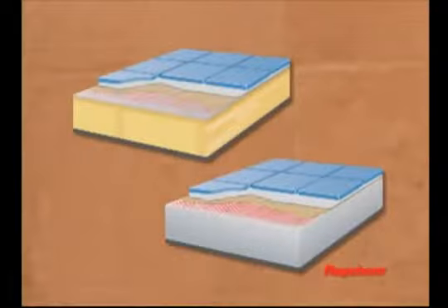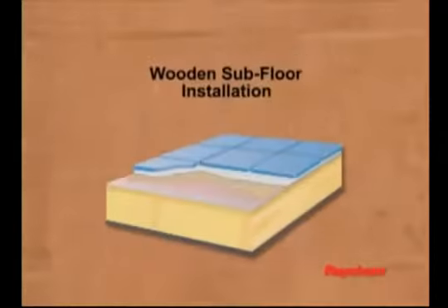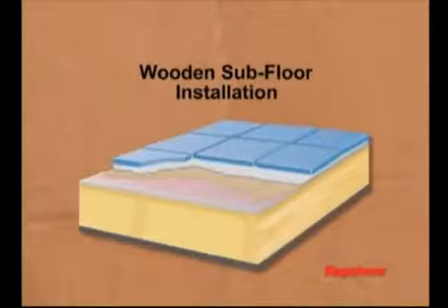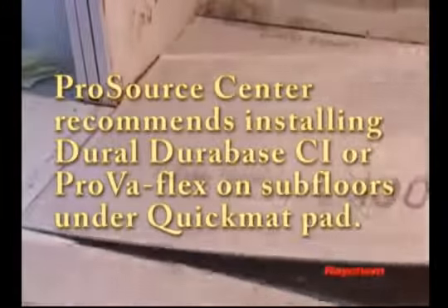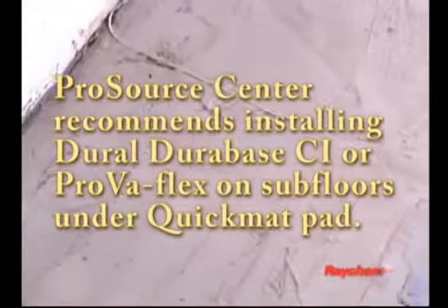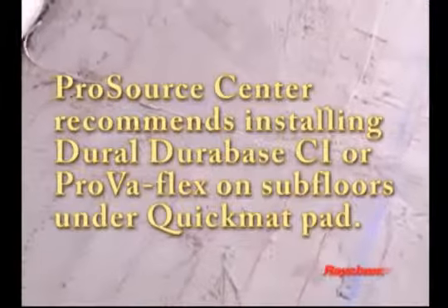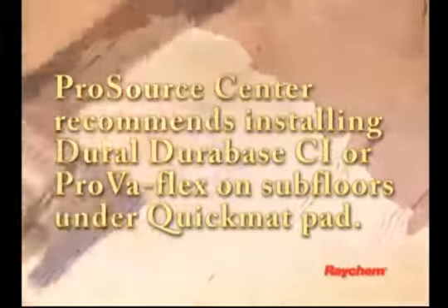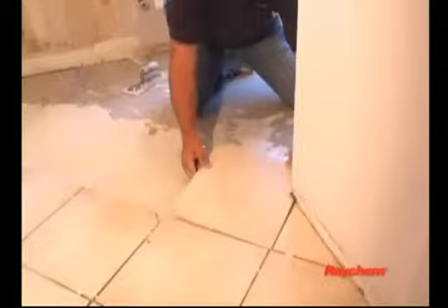Quickmat floor warming mats can be used on typical interior floor constructions using tile or natural stone. The typical construction is either a wooden subfloor or a concrete slab. For installation on a wooden subfloor, it is typical to have backer board, the Quickmat mat, and floor temperature sensor embedded in a mortar bed, covered with thin-set mortar, and finally, ceramic tile and grout.